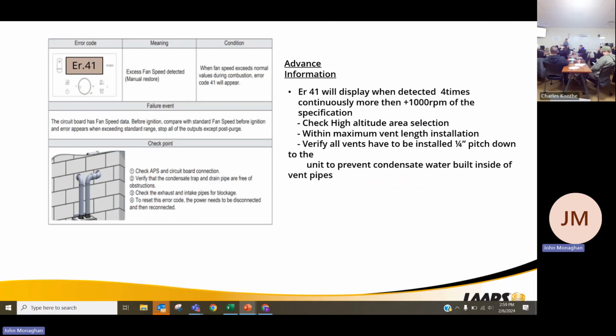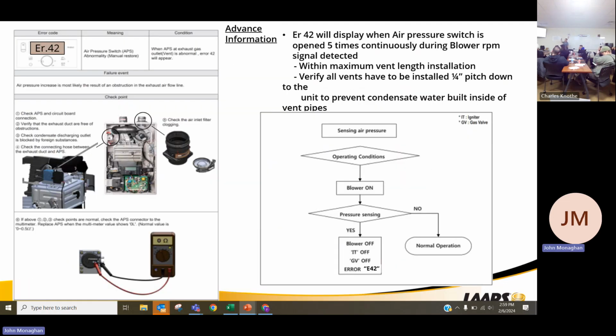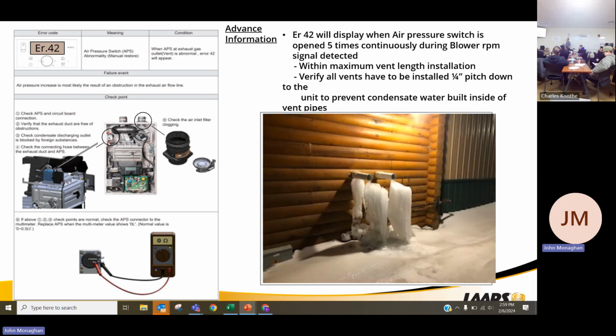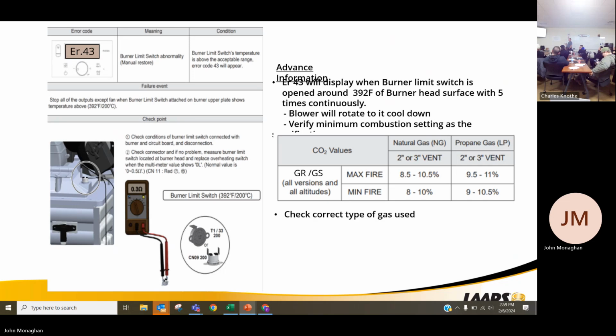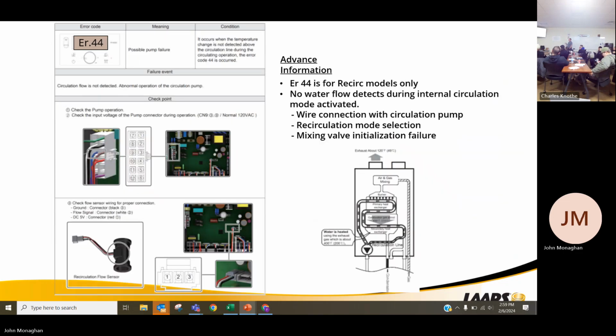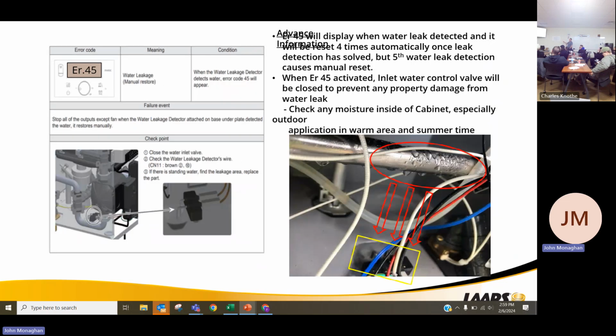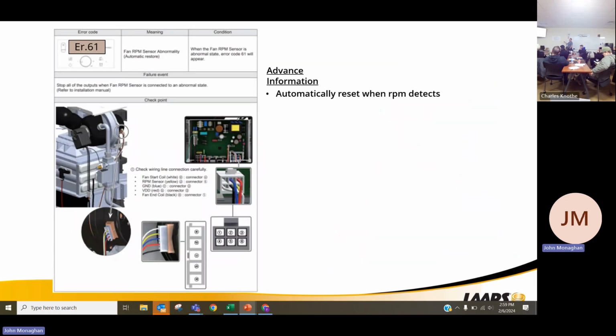Again, these are multiple slides of troubleshooting that we probably don't need to go through slide by slide, but it'll go through like your error 42. Basically, it's a blocked vent. We can go through and test the transducer to see what we're doing, or check to see if the unit's filled up with condensate or if the vent actually is blocked. And there it goes, showing your vent blocked. We want to take care of these things freezing. We want to pitch them back towards the boiler. We have that condensate pump there for a reason. We don't want to pitch them outside, because then it gets cold and we get these wonderful ice features outside of our homes, which we don't want. Got to adjust some of them, but all the troubleshooting, all the pieces are in there. The slides, I guess, got jumbled together.